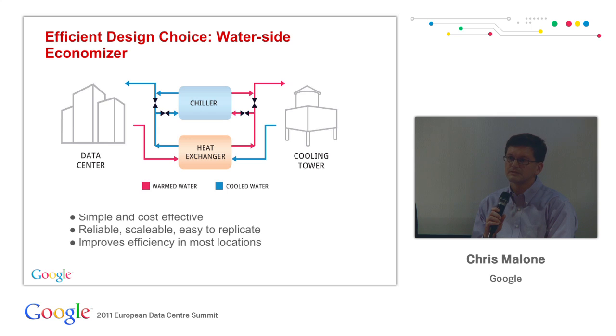What I'm showing here is not an engineering drawing, but a cartoon representation of one of our favorite cooling plant designs. To echo James's point, we're a big fan of utilizing economizers and minimizing the use of mechanical cooling whenever possible. This design achieves that by putting a heat exchanger in line with your chiller. A very simple concept: the hot water returning from your data center floor meets the cooling tower, and if it's sufficiently cool, you don't actually need the chiller, or you can minimize the amount of chiller tonnage required.